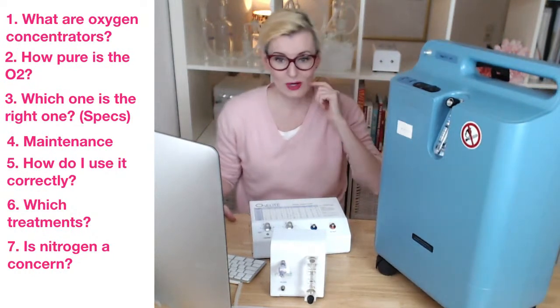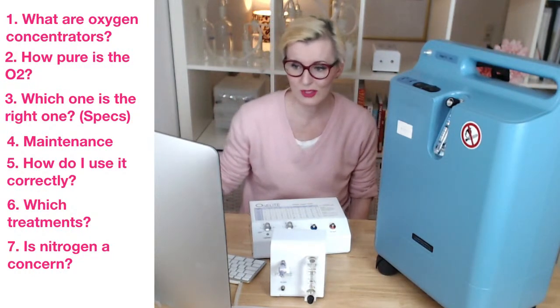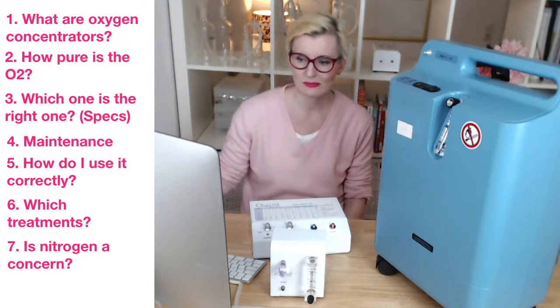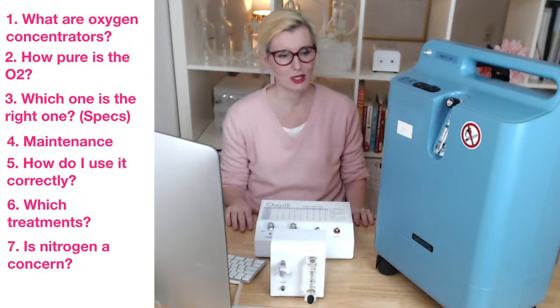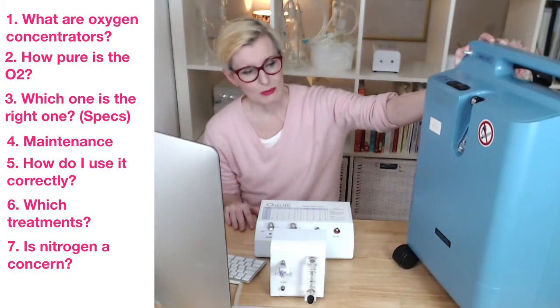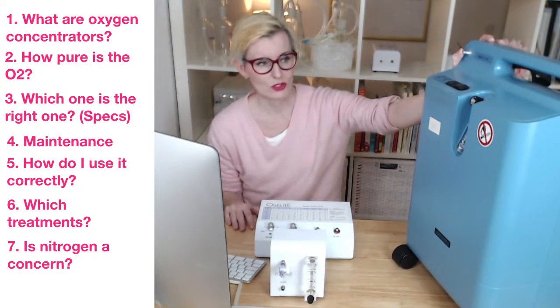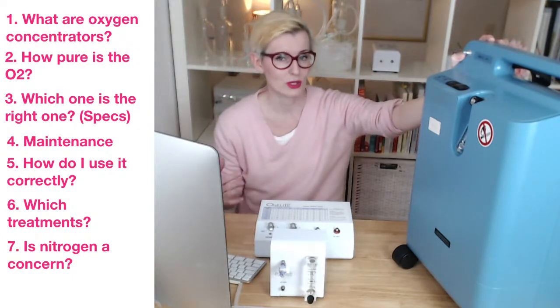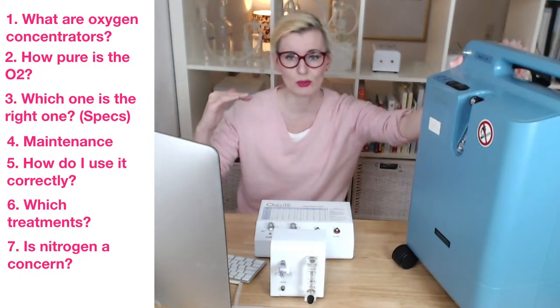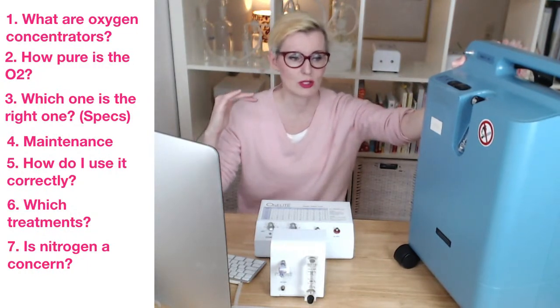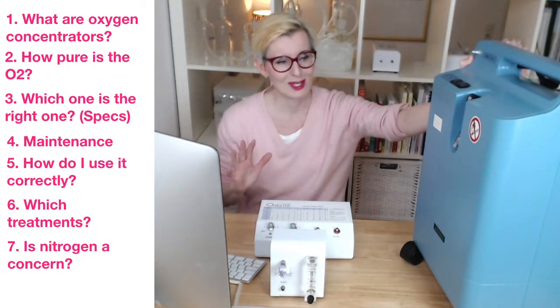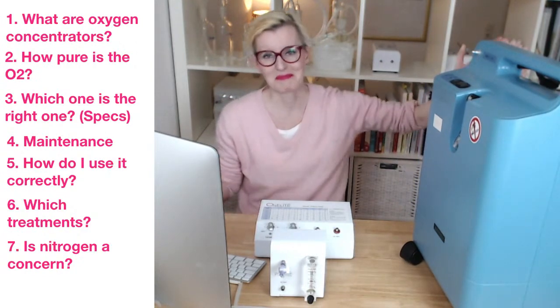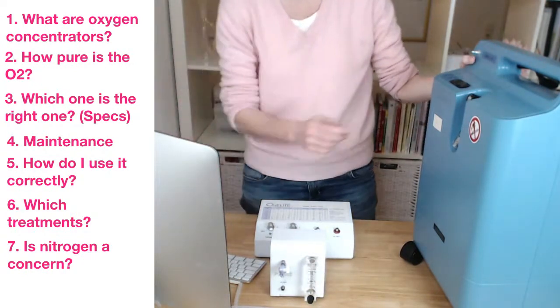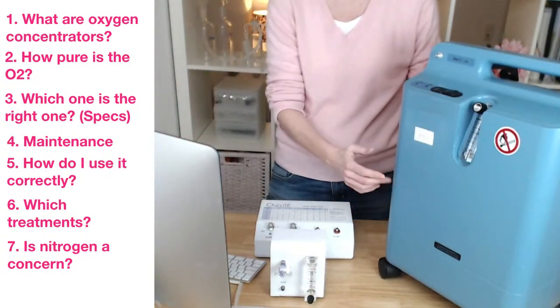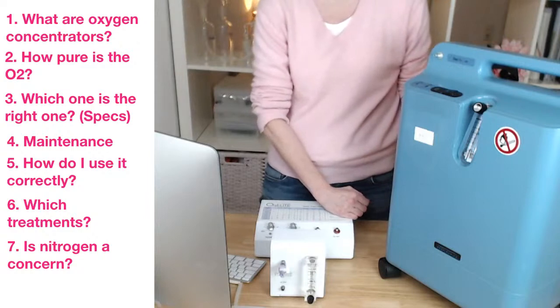So yeah, this is the great thing about oxygen concentrators: they're very, very low maintenance. Okay, now how do you use it correctly? So here's the thing. Before you use the oxygen concentrator, you should let it run for at least 10 minutes, because that's how long it takes for the machine to start producing maximum oxygen output. And I have to admit that I don't always keep to this. I don't have that much patience, but this is the correct way to go about it.